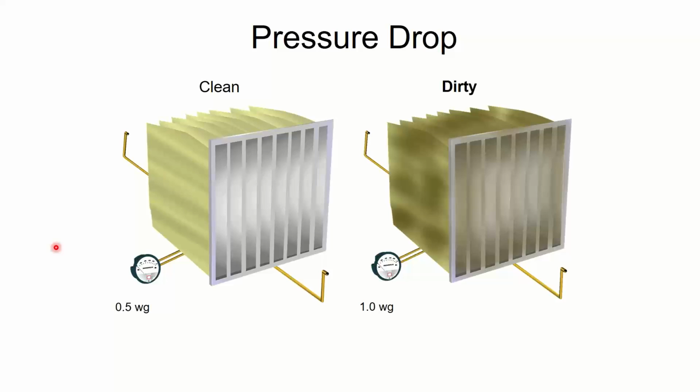But I've had it over the course of 5 years. I've had it last 11 months, 9 months, 15 months, 13 months, I think, are the months that I changed it at based on pressure drop. So I got some pretty good usage out of that. Before that, I had much simpler, cheaper filters, but they didn't load as well as the expensive one, and I would have to change them more frequently.